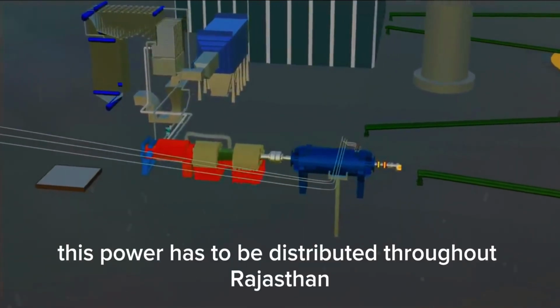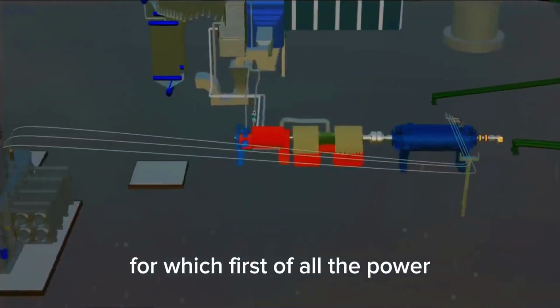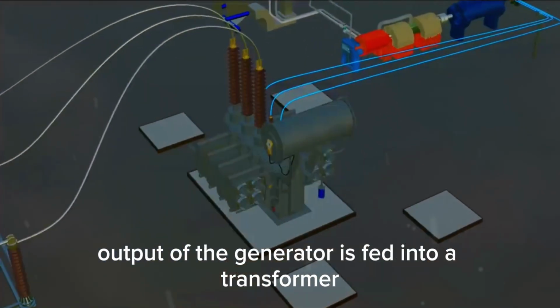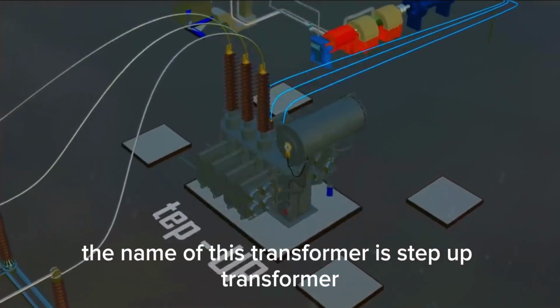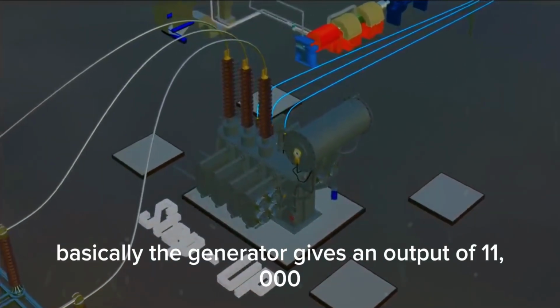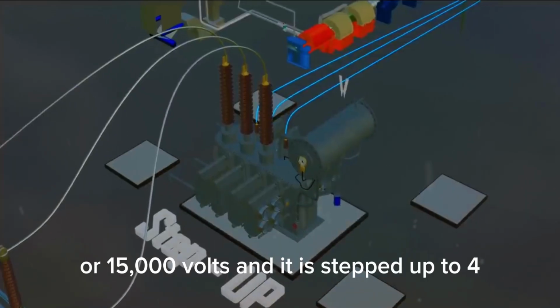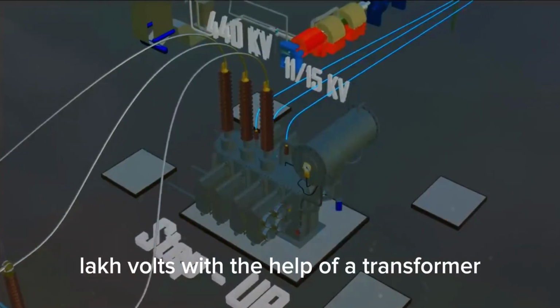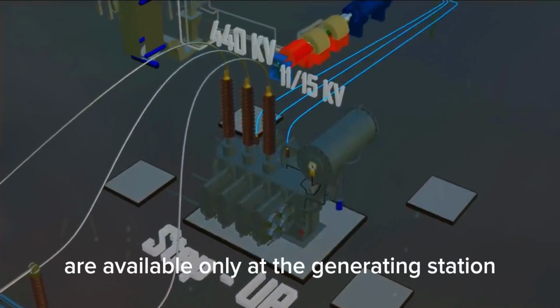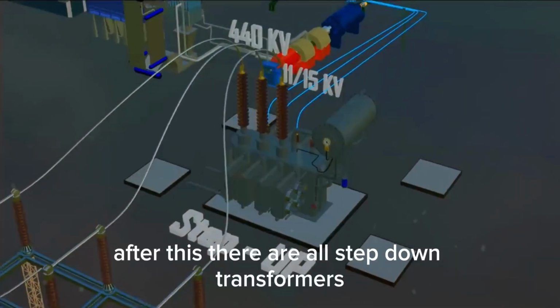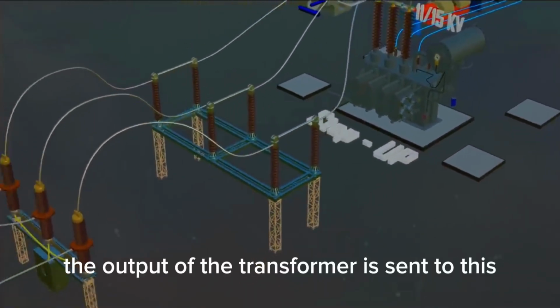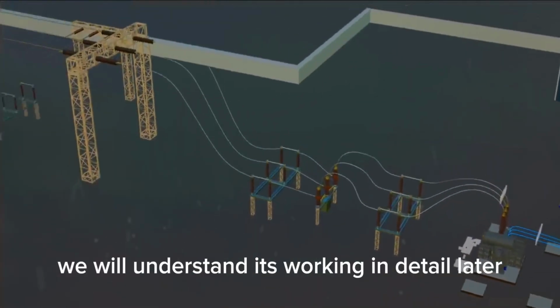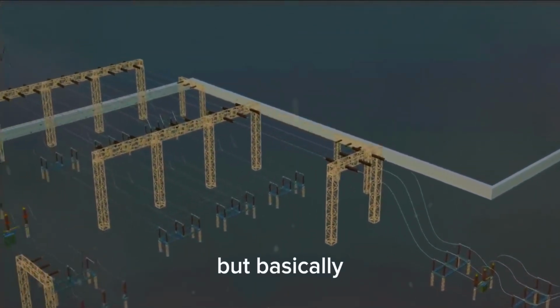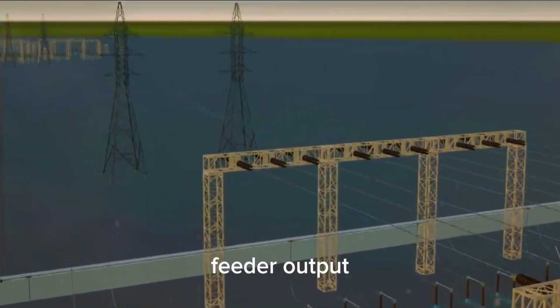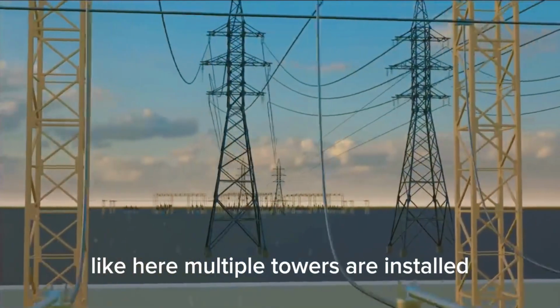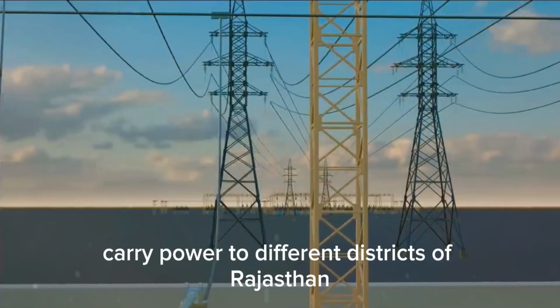Now this power has to be distributed throughout Rajasthan, for which, first of all, the power output of the generator is fed into a transformer. The name of this transformer is step-up transformer. Basically, the generator gives an output of 11,000 or 15,000 volts and it is stepped up to 4 lakh volts with the help of a transformer. Mostly step-up transformers are available only at the generating station. After this, there are all step-down transformers. The output of the transformer is sent to this switchyard. We will understand its working in detail later. But basically the work of the switchyard is that it gives multiple feeder output. Like here multiple towers are installed and all these towers carry power to different districts of Rajasthan.